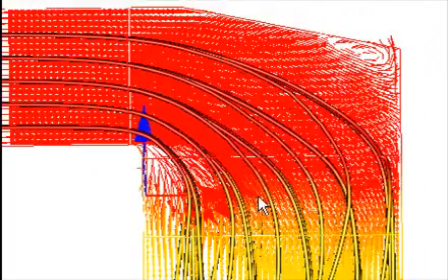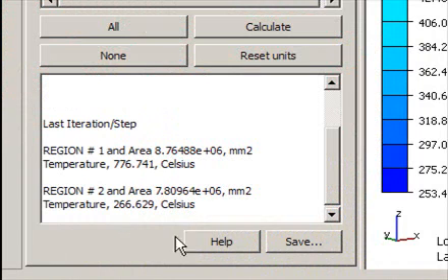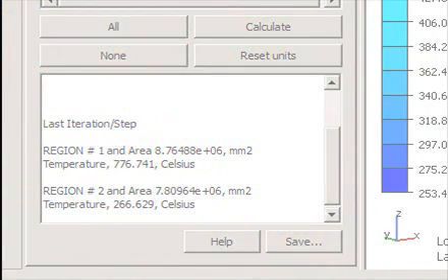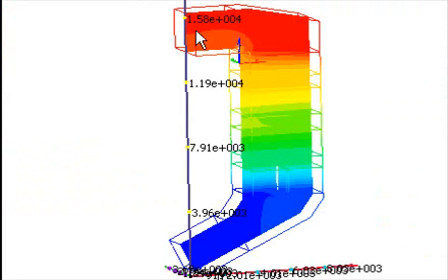The thermal management calculation showed 269.3 degrees C flue gas temperature after the economizer. Our simulation presented 266. The error is around 1%. That's quite nice. We can check all pressure losses on the heat exchanger blocks.